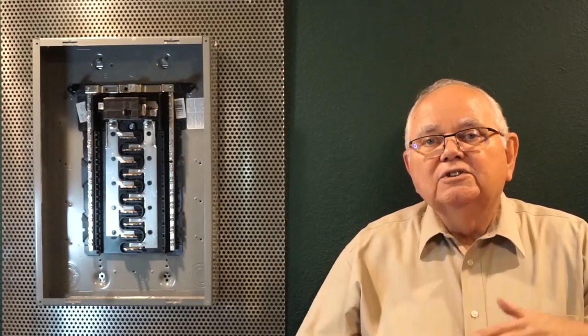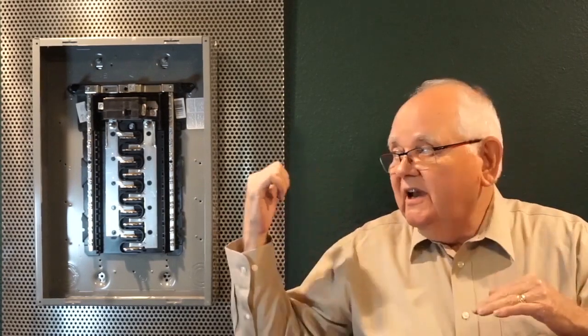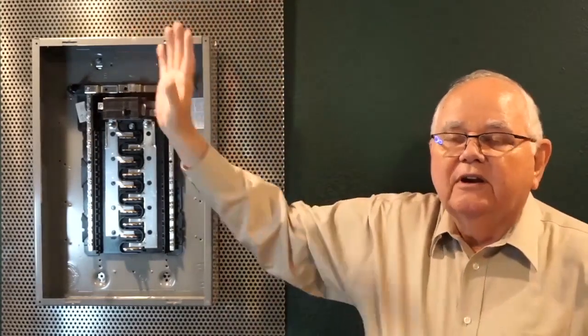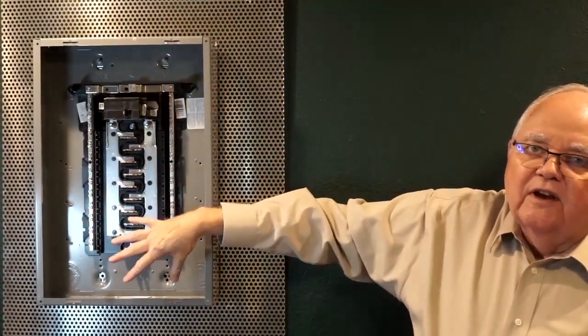If I'm not comfortable that I can do this job safely, I go to the next step, the third step. What can I do in order to reduce the risk inside of this panel so that I feel that there's minimum likelihood, and if something does go wrong, I will not be injured at all? If I cannot feel comfortable, if I do not feel safe, I'm not going inside of that panel. We're done. If there's no way to work safely on this equipment, we don't work on it until we de-energize upstream or whatever it is we have to do, obviously. Okay. So we said this is a feeder panel. We've locked out and tagged out the upstream breaker. We need to verify that this panel is safe to go inside of and maybe replace some breakers or whatever.